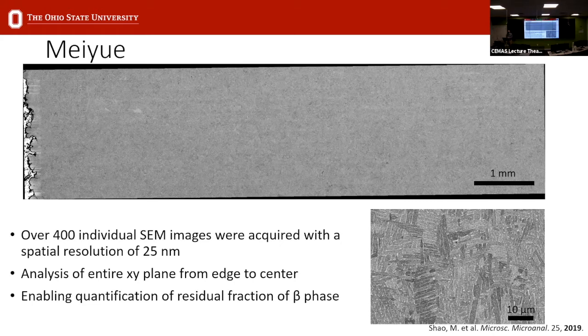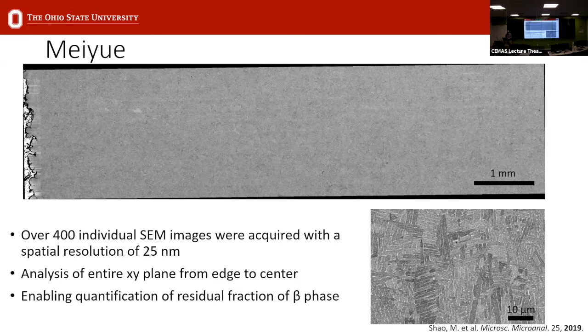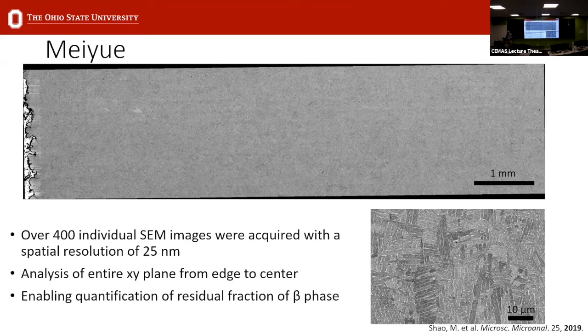The caveats of this work: to get images of sufficient quality, it took 8 to 10 hours to collect overnight. It can be a significant time sink. The final stitched dataset was about 20 gigabytes — essentially impossible to analyze on most systems as a whole — so it had to be broken back into sections for analysis. When doing this kind of work, really think about what data you need, what's the lowest resolution you can actually use, and plan your data analysis workflow and instrument time accordingly.